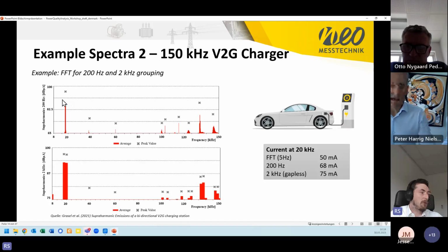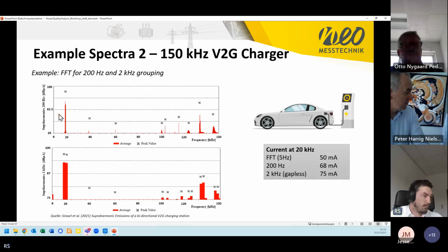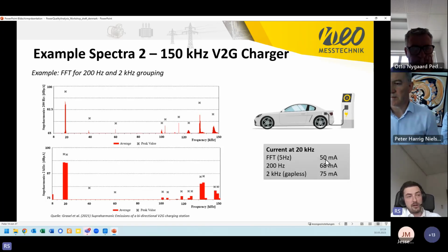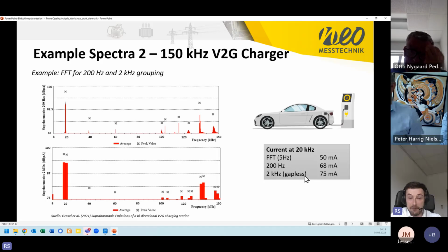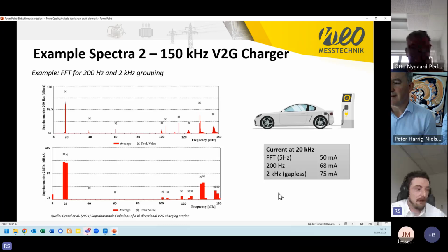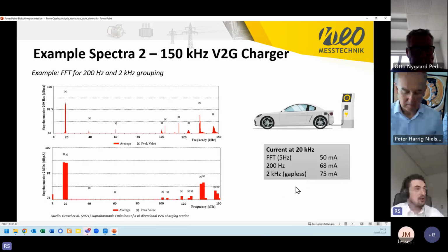If we talk about the value itself, for example at 20 kilohertz, we see from the raw FFT - the 5 hertz output of the FFT, from 4.7, before the grouping starts - a value of 50 milliamps at 20 kilohertz. If we do the 200 hertz grouping, we see 68 milliamps. And the 2 kilohertz gapless method - to mention, it's a little bit different to the original definition, because the original definition of IEC 61000-4-30 edition 3 just uses parts of the signal and then does the FFT. But here the gapless method is implemented in our system, which gets more precise, but also gives a different value again - we see 75 milliamps. So between 50 and 75 milliamps, this is quite a difference already.